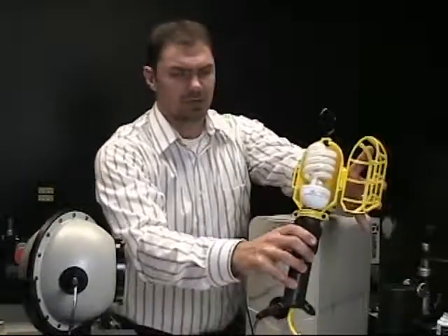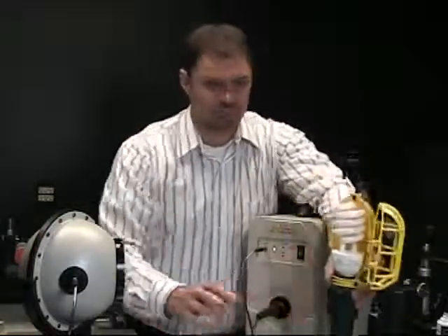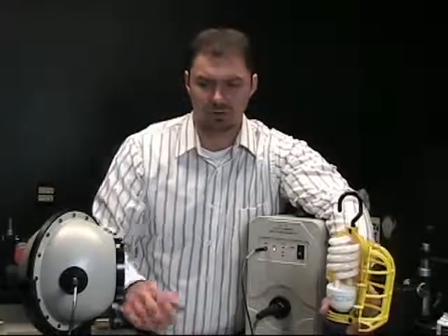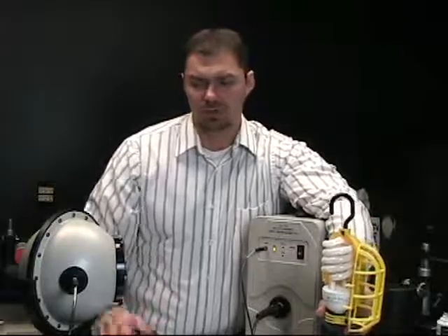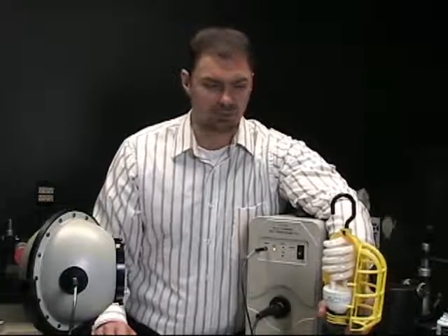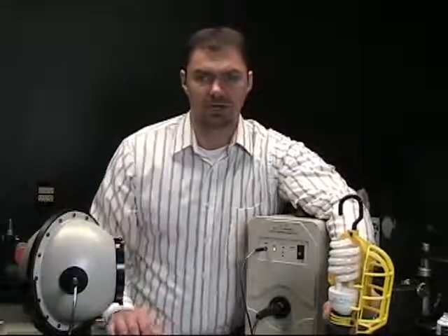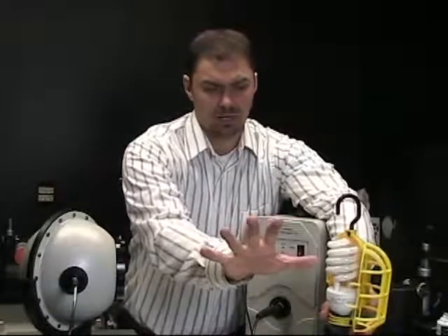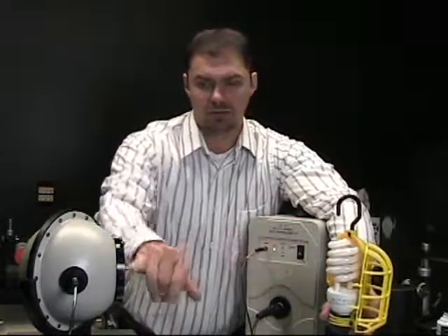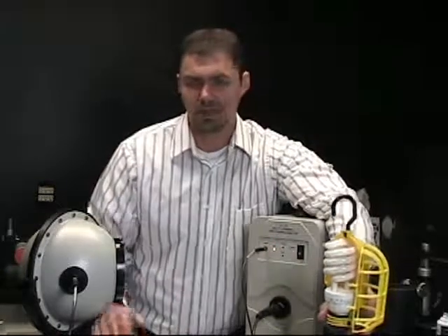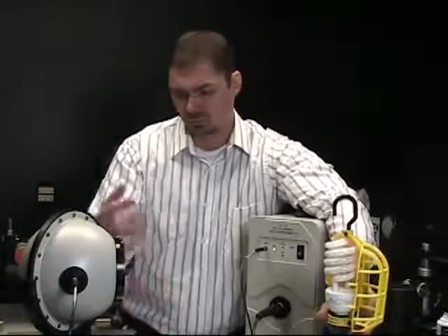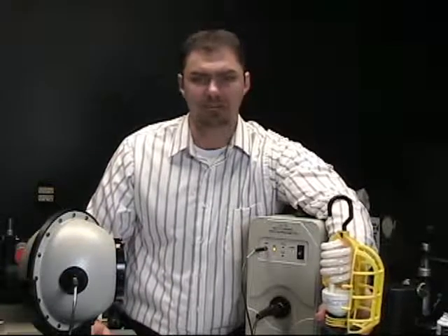So essentially what we need to do now is look at a fluorescent lamp. We need to align the lamp both in the X and Y direction with the center line of the port, leaving the same configuration we had before. Because this is a radiant intensity measurement, you want to measure the distance from the lamp to the port very accurately. Once this is all set up, you would move into the software portion and perform a spectral radiant intensity measurement. We'll move into that right now, and I'll show you some screenshots.